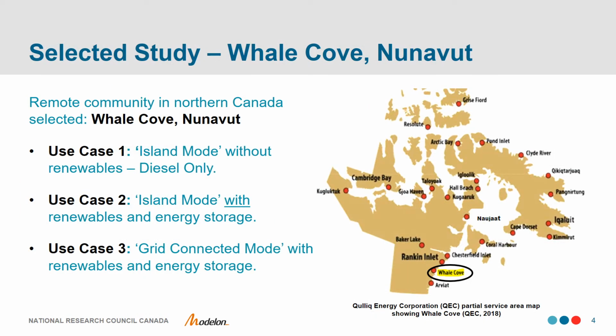To work with this integrated system model, a case study was devised consisting of 3 different use cases for a remote community in northern Canada, Whale Cove, Nunavut, shown circled on the right. Use case 1 represents Whale Cove's current configuration, a remote microgrid with no grid connection and 100% reliance on diesel generator power. The second use case considers the impact of adding renewables and energy storage to the existing microgrid. And the third transitions the microgrid from island mode to grid-connected mode, with a grid tie to a neighboring provincial utility. For renewables and energy storage, the technologies currently planned or included in the NRC facility power network were explored to see how they might benefit the existing Whale Cove microgrid. Multiple design, economic, and environmental analyses were then performed.